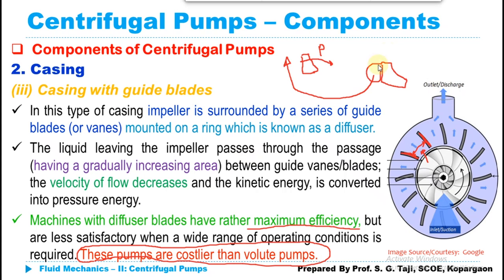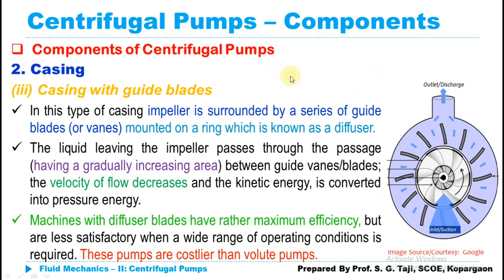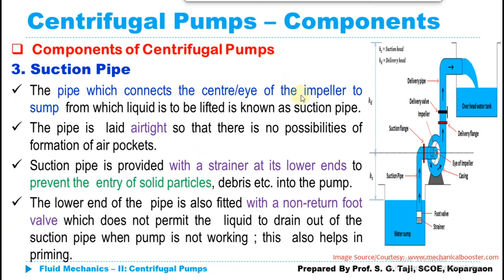The suction pipe connects the eye of the impeller to the water sump or source. It comes with a strainer at the bottom to prevent entry of debris or suspended solids that could damage the impeller vanes, and a foot valve which acts as a non-return valve preventing back entry of water when the pump is off. This pipe is generally airtight because it needs to develop suction head, and it takes water from the source toward the eye of the impeller.